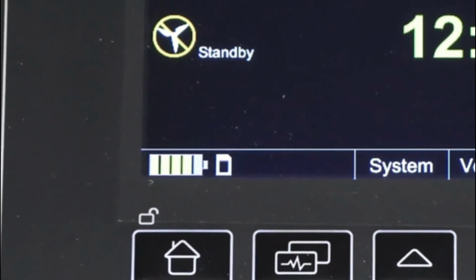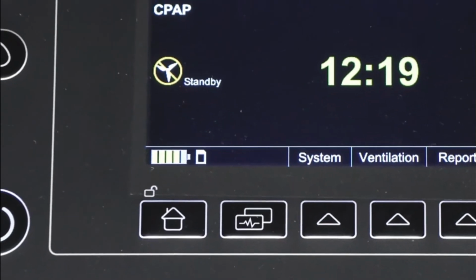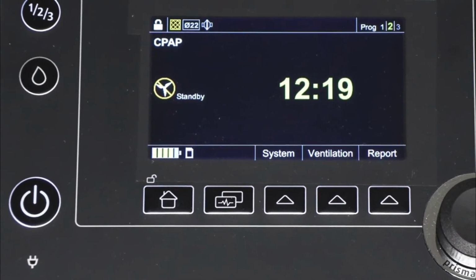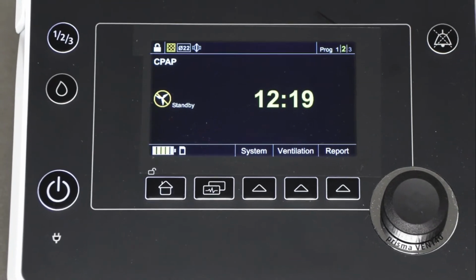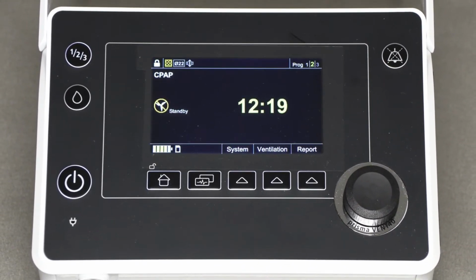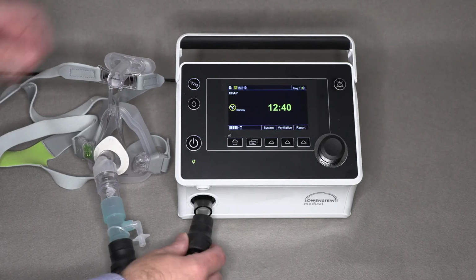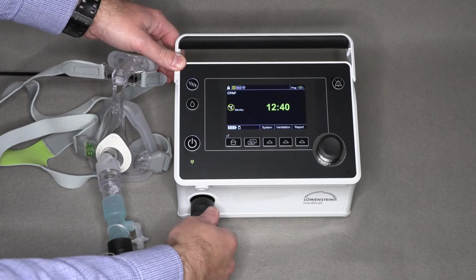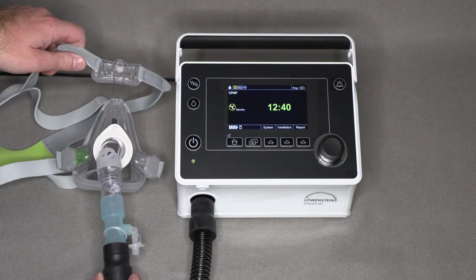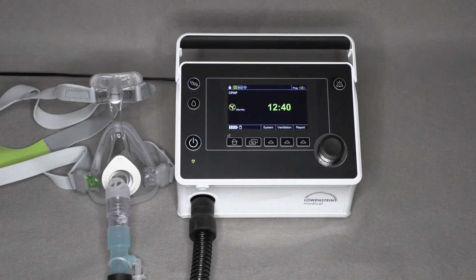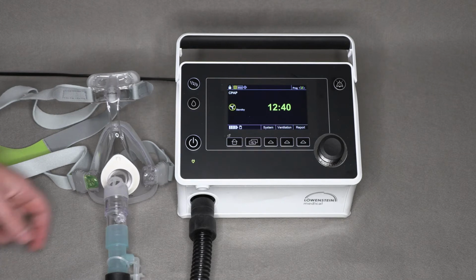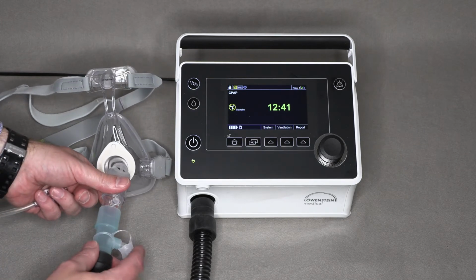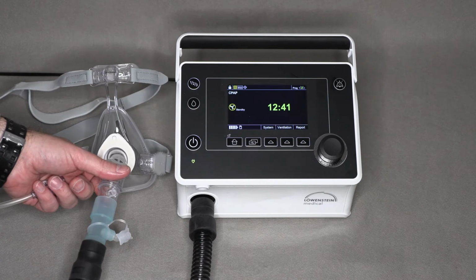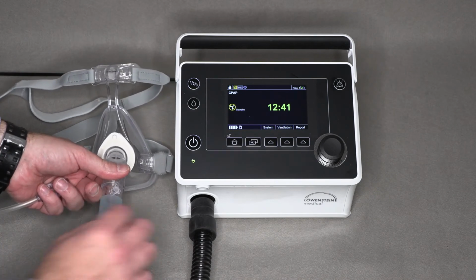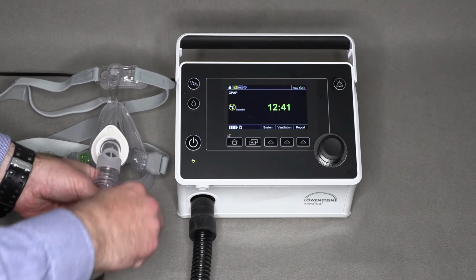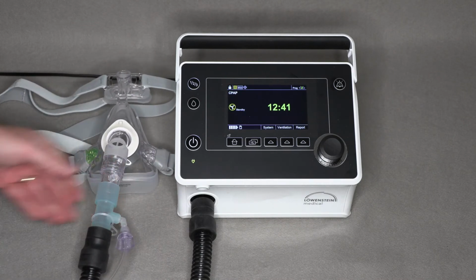Although prismaVENT does have an internal battery that is kept charging once the ventilator is connected to electricity, it should always be operated from mains power to avoid running down the battery. Ensure that your breathing tube is connected to the outlet at the front of the ventilator and your mask is connected to the other end of the breathing tube. If you require oxygen to be attached, ensure that an oxygen fitting is between the mask and the breathing tube and an oxygen tube is attached. You'll also need to make sure that you turn on your oxygen supply.